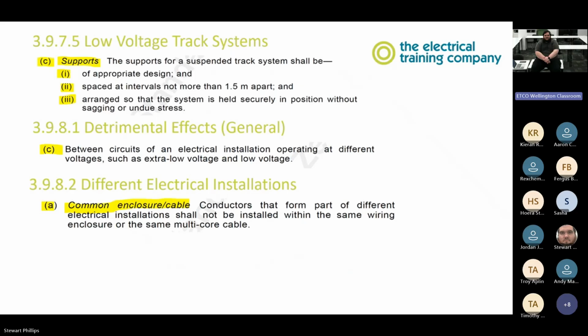So one example is you may have a cable that comes from, say, the second floor of a building down to the first floor. To ensure that, even if that cable is running through the other installation, we must make sure it is in a separate cable enclosure.